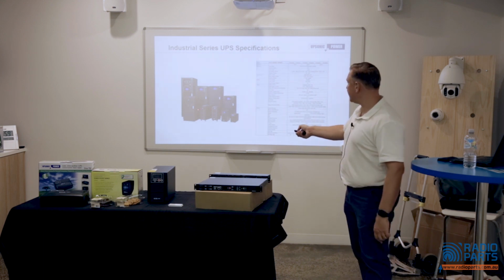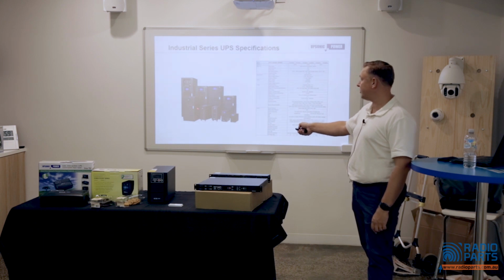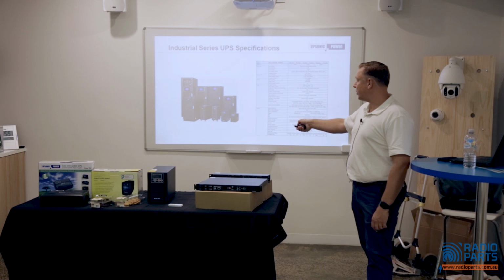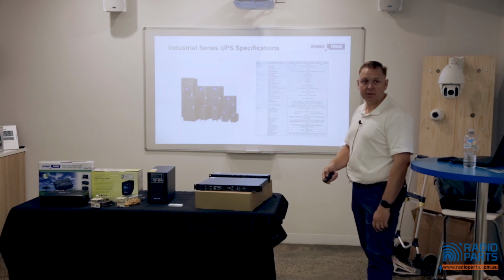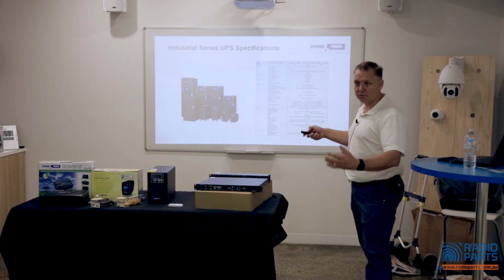If you look, the picture's a little dull, but these also have space for internal batteries. That frame size is the same whether it's a 10, 20 or 30 kVA three phase - they just have varying degrees of space in the bottom for internal batteries. With the others, the batteries are all external.